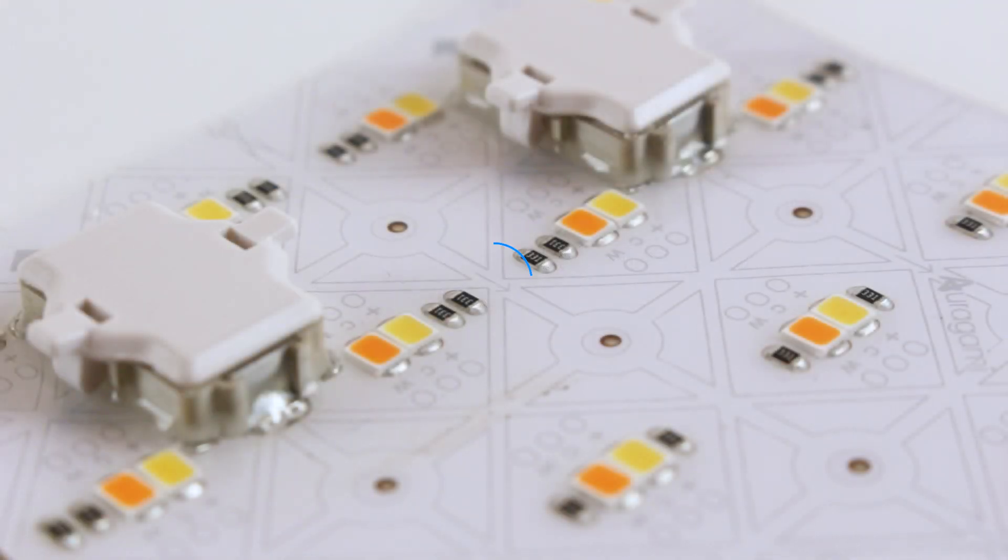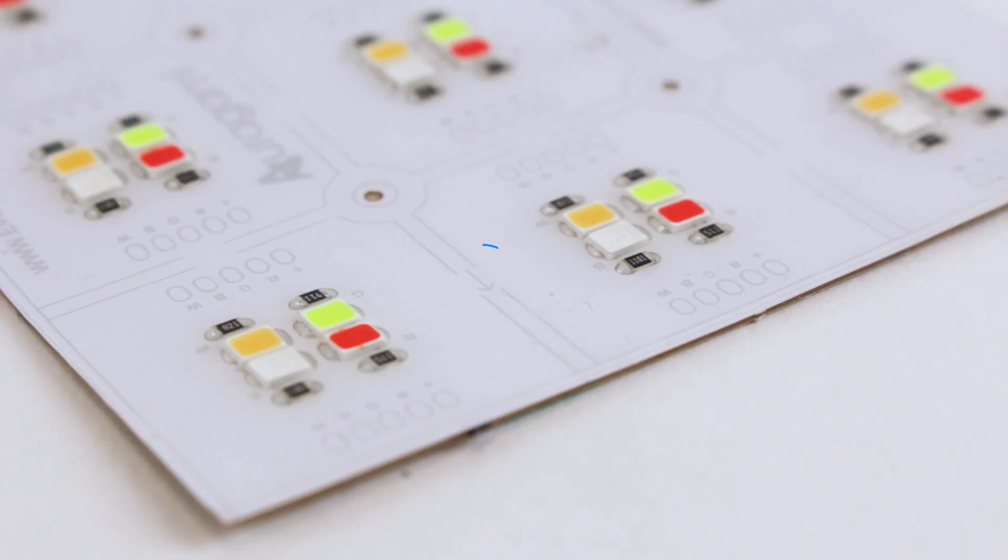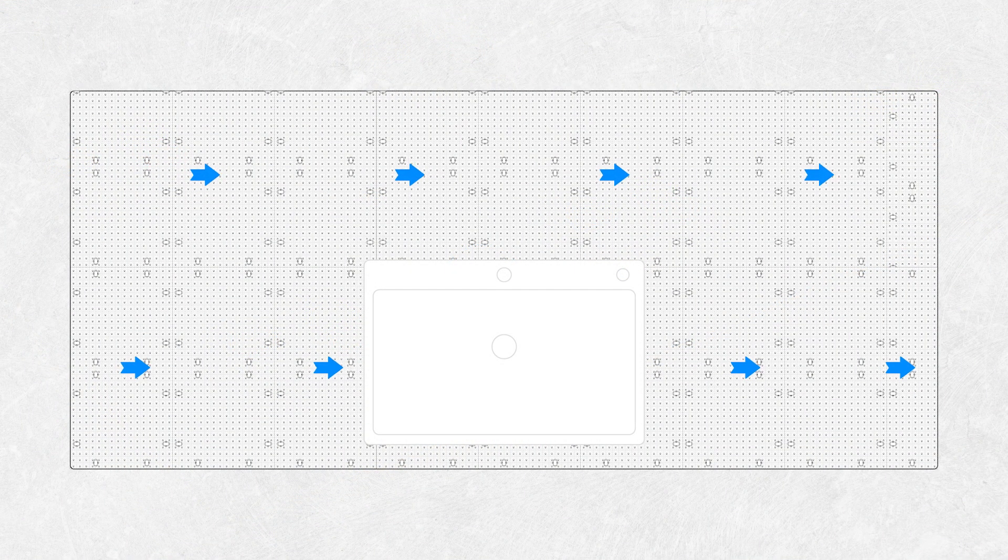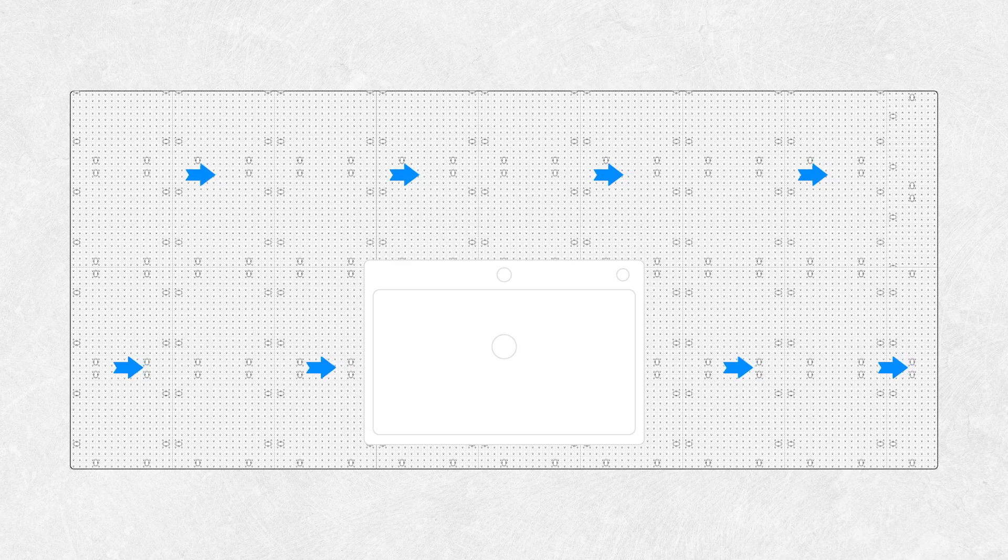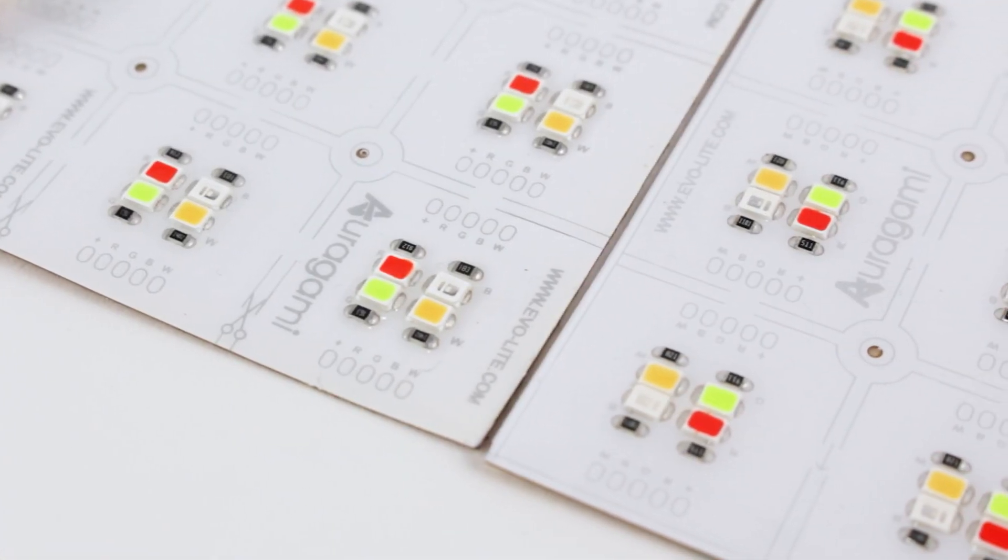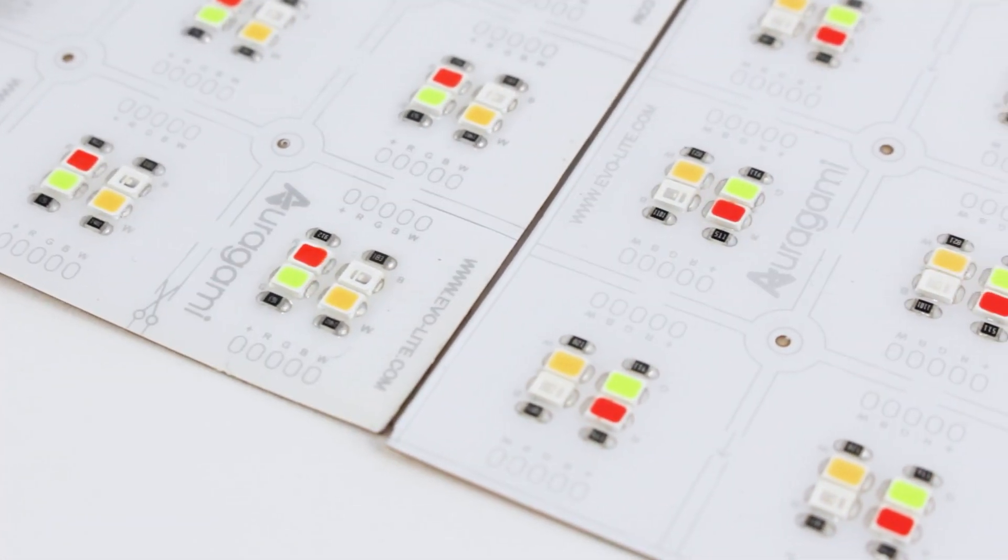Tunable white and RGBW lightsheets have orientation arrows printed on them. Install contiguous sheets with all of these arrows pointing in the same direction. Failure to orient these lightsheets consistently will cause adverse color effects.